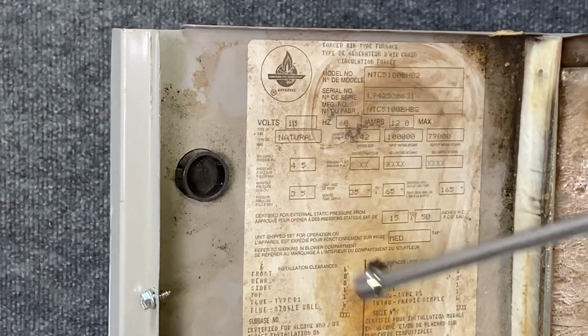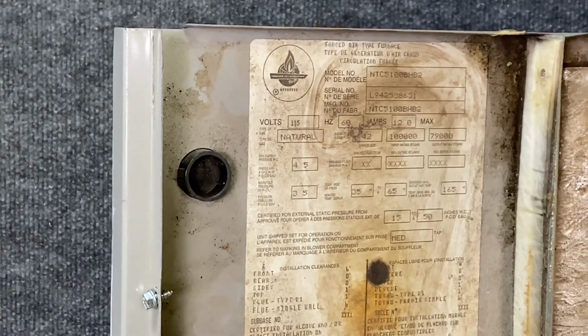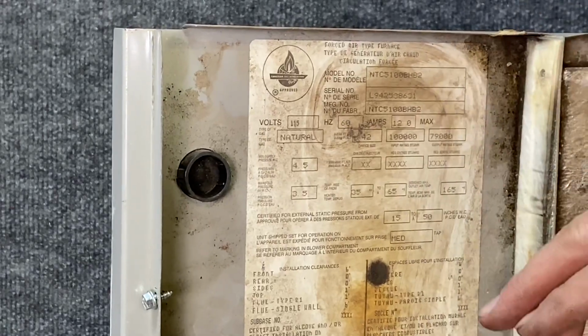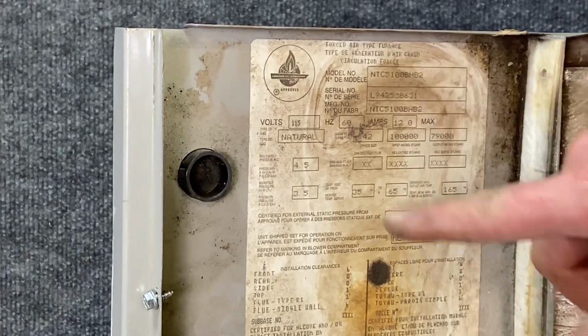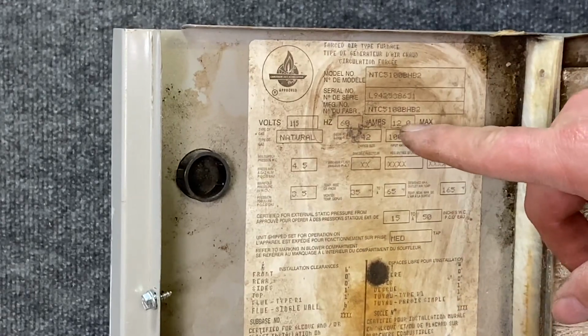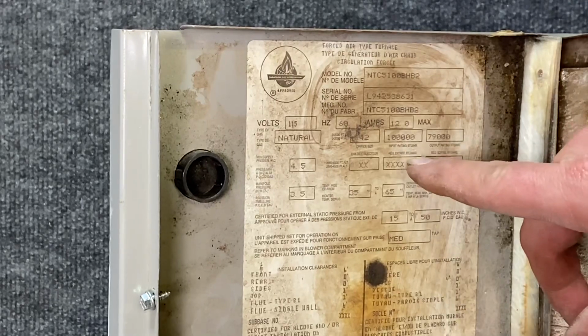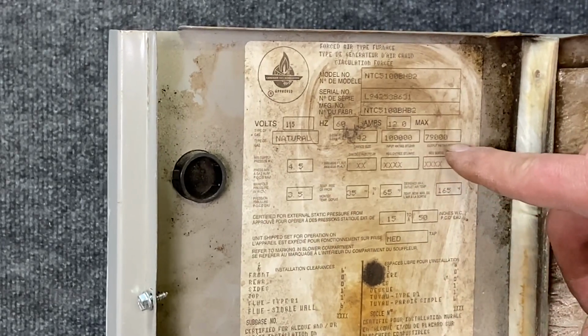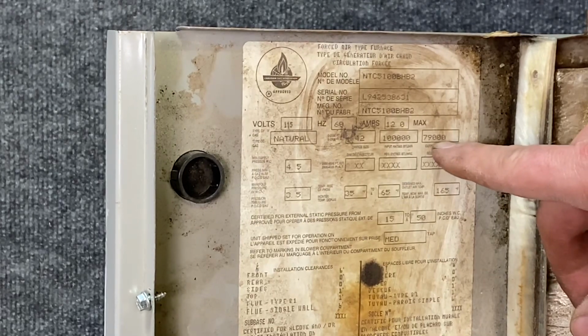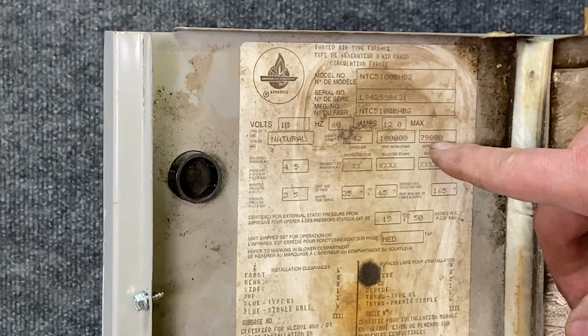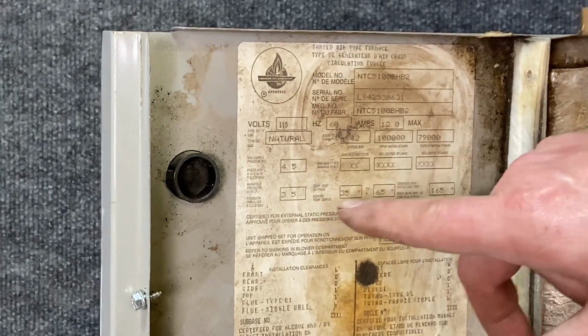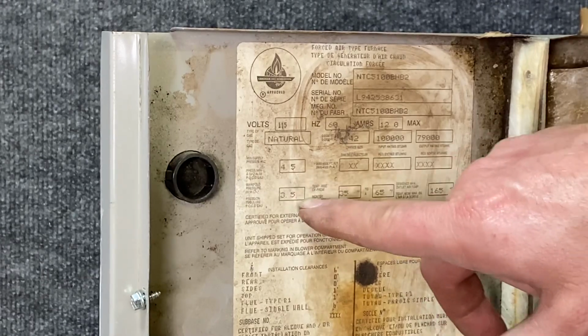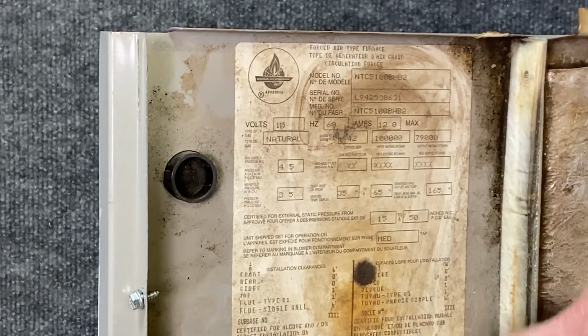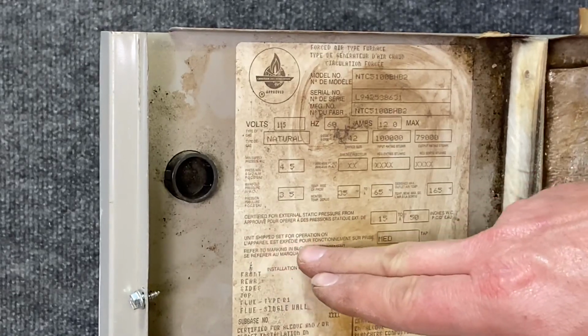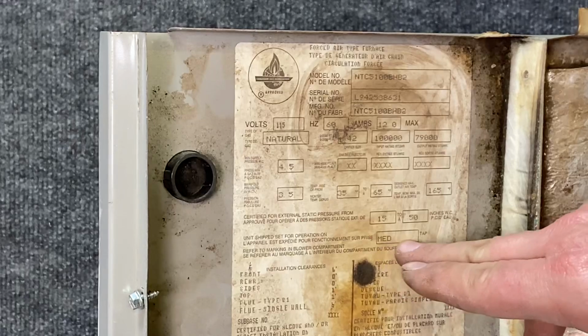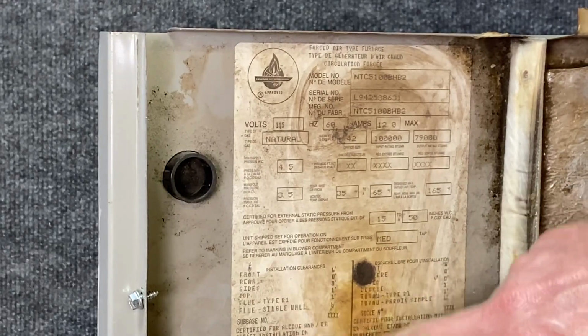This furnace is a horizontal, so this is the bottom side, and this is pretty dirty, pretty icky. If I try cleaning this, I'm afraid the numbers would wash off of it. But a lot of the same exact numbers as the other side. It does clarify 115 volts, 12 amps maximum, no more than 12 amps, 100,000 BTU input. The output is set for 79,000 BTU, so it's actually a little bit less than an 80% furnace, probably a 79% furnace, I guess, instead of an 80%. And over here we have our gas pressures in, manifold pressure, same information as before. The limit switch for operation is for fan on medium speed on the tap, and I can't really read too many of these other numbers.